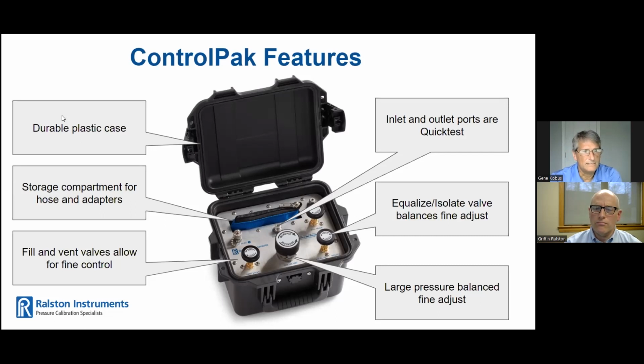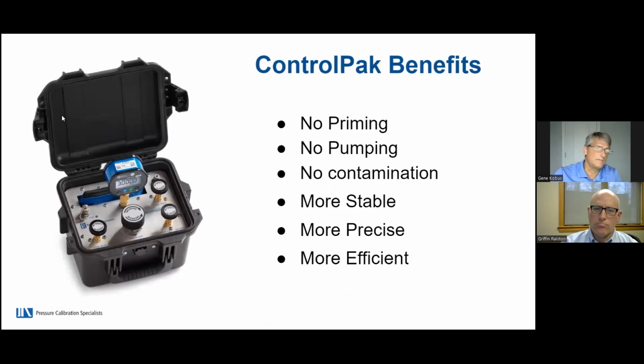The equalize and isolate valves let the user equalize large-volume, fine-adjust pistons so they can have very precise control of pressure, whether it's 0.003 psi or 3000 psi. The fill and vent valves are both metering-style valves, which means the user has excellent control when increasing or decreasing test points. The ControlPak also has a convenient compartment to hold a nylon bag for your hoses and adapters. Some of the benefits of the ControlPak: it's more stable.